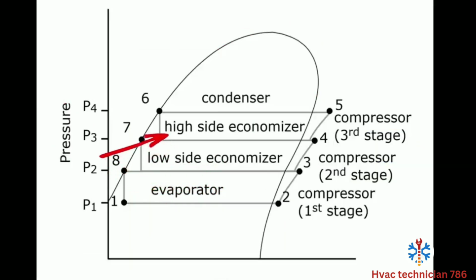Now, to show you what this looks like from the CVHE perspective, or CVHG, we leave our condenser high pressure liquid. We hit here to this point. This is where we go through the first flash plate in the high pressure side, or the high side of the economizer chamber. We pull that flash gas off. We go through the second stage flash on the low side of the economizer, and we pull that flash gas off, each time returning that liquid refrigerant to a fully saturated refrigerant and dropping the enthalpy. And then we're able to actually send it to the evaporator and have far more effectiveness.